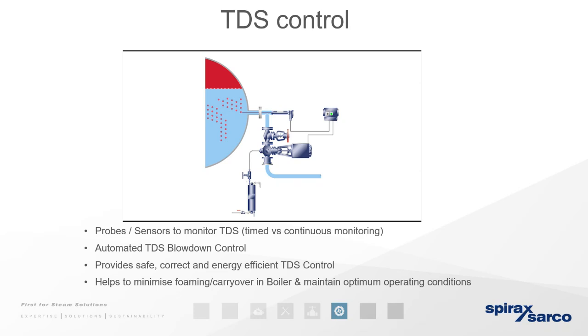It will depend on the plate values that you have in your processes themselves. And as Cornelius said, it is to prevent forming of scale and things like that on boiler surfaces. So, for instance, to add on to that, a 1 mil thick layer of scale can result in insulating efficiency, which means it would cost you up to 10% more fuel because of the scale, because of high TDS. And foam being drawn out of the boiler onto the headers and down into your system will lower the energy that's available, and cause erosion, corrosion and water hammer in your system. Hopefully that answers that question.